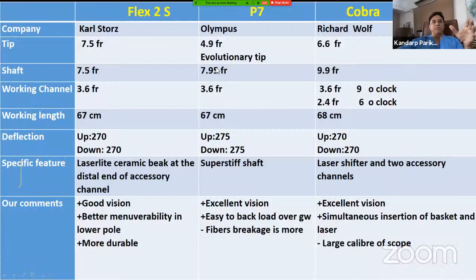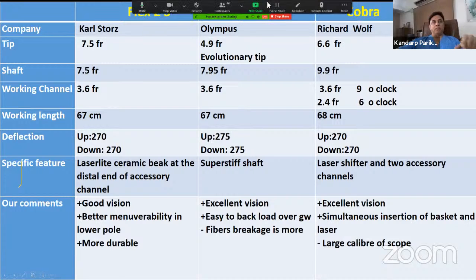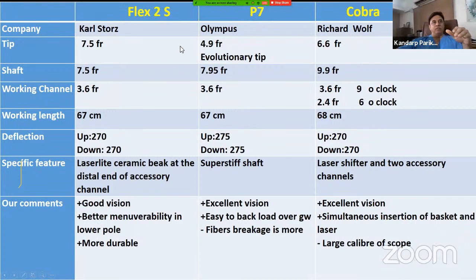This is just to give you an example of what kind of flexible fiber optic scopes are available in India at this moment. We have the FlexX 2S from Karl Storz, P7 from Olympus, and Cobra from Richard Wolf. FlexX 2S and P7 have almost the same parameters and specifications, except that in FlexX 2S the tip has a laser light ceramic beak covering the last 1.5 centimeter of the accessory channel. This ceramic beak will prevent injury to the accessory channel if you accidentally fire a laser. So that's a very, very important feature of this scope.